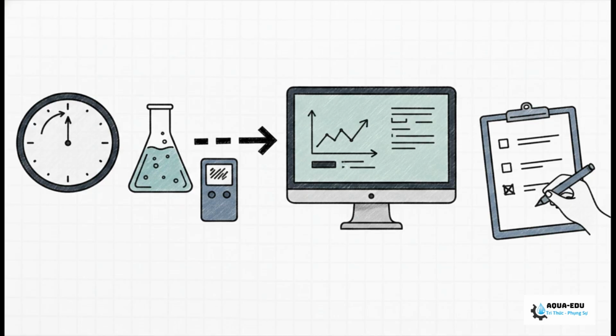During this window, take a physical sample in a glass beaker and compare the screen output directly to your handheld DPD colorimeter. We are demanding less than a 2% deviation full scale here. Check your SCADA monitor to ensure the 4-20 mA signal is pushing the exact same value to the control room. Once that's all confirmed, sign off every single item on your handover logbook.